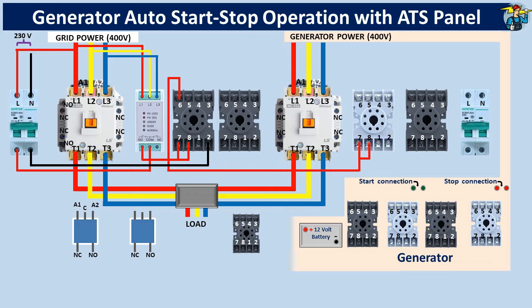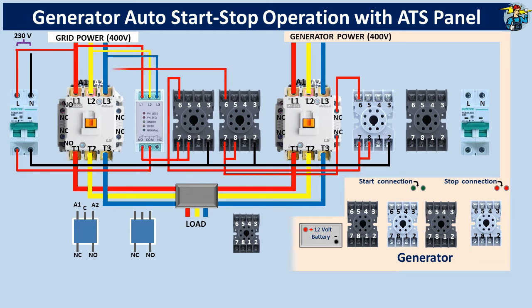Number 7 should also be connected to common port number 8. The neutral line on the grid side is connected to number 2 of the relay. Output port number 6 will go through the normally closed auxiliary contact points of the generator side contactor to port number 7 of timer number 2. Number 7 is connected to common port number 8. The neutral line on the grid side is connected to number 2. Output terminal number 6 is connected to the A1 coil end of the mains contactor. The neutral line on the mains side is connected to coil end A2. On the generator side, bring a phase line to the double pole breaker.